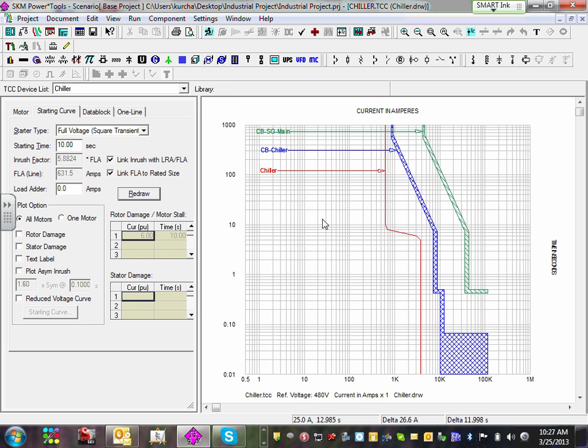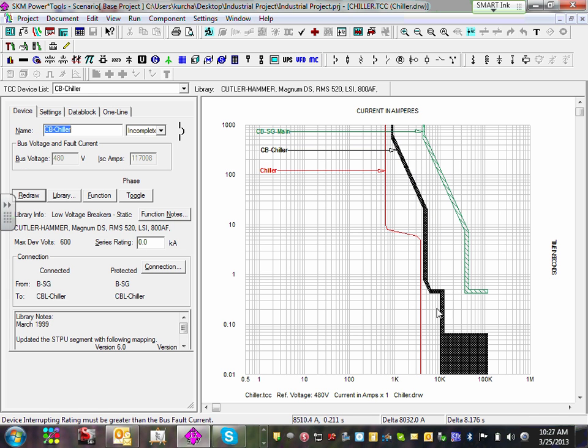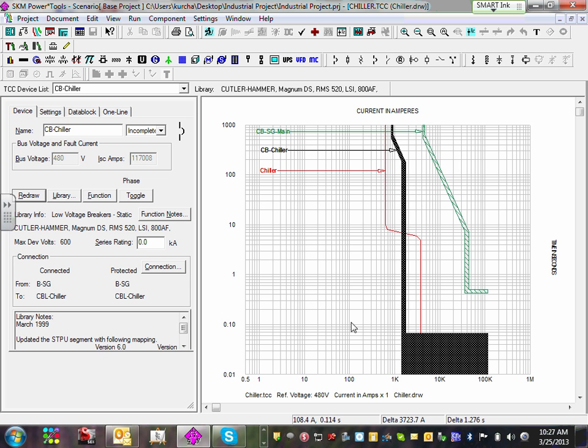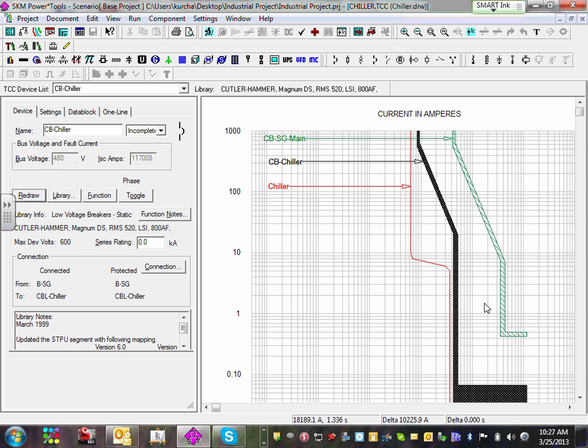Now your job is to make the adjustable circuit breaker as close to the curve as practical. Look at this - I'm going to grab it instead of moving away from it. The best protection, guys, is if you get it as close as you can without overlapping. So I'm going to grab it - look at that. This is bad, that will not allow the motor to start. So I'm going to drag it just slightly - there you go - to allow it slightly to start.